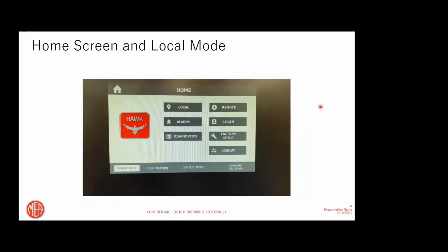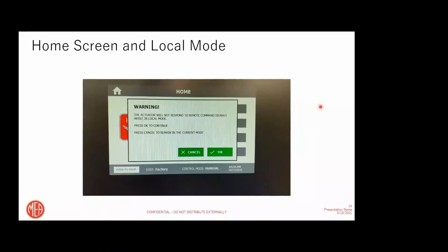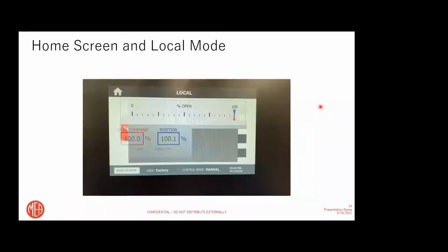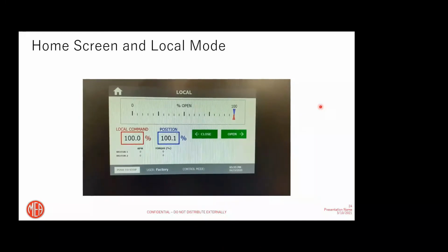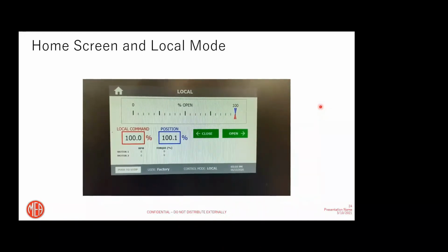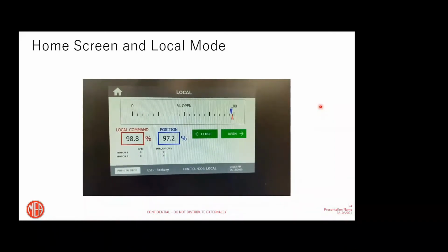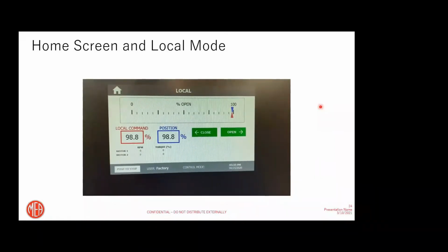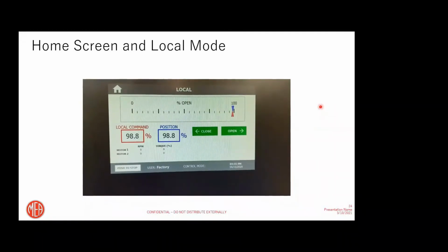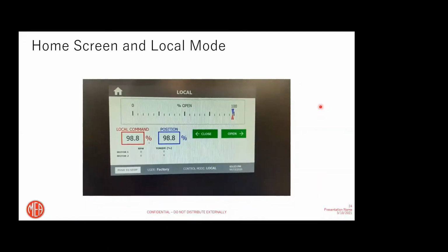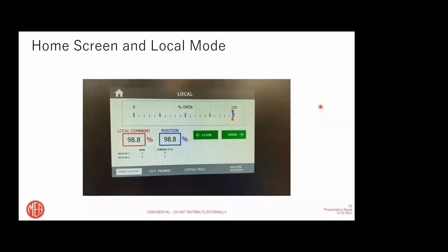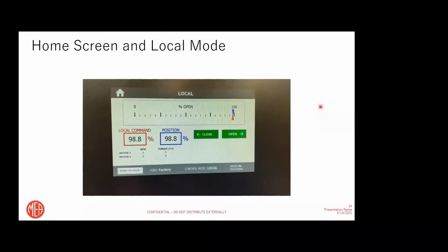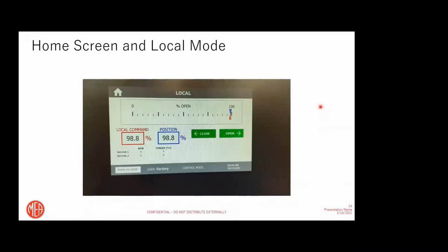First, we'll jump into local mode. Local mode is similar to remote mode in that it relies on a control signal to drive the motion, and that control signal must be active at any given time. It's also a combination of manual, in that the user gets to close and open the actuator using these two push buttons. You will have a readout of the local command, which is essentially the control signal, and the position feedback, which tells us where our actuator has moved relative to the command signal that we provide via these two push buttons.